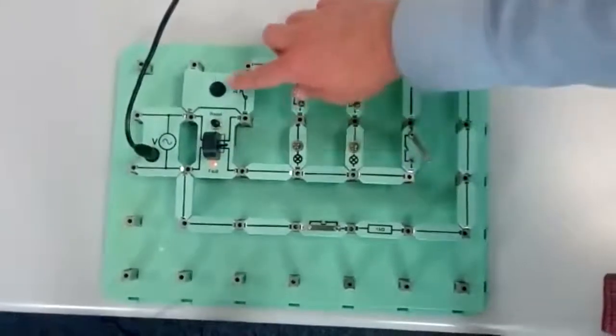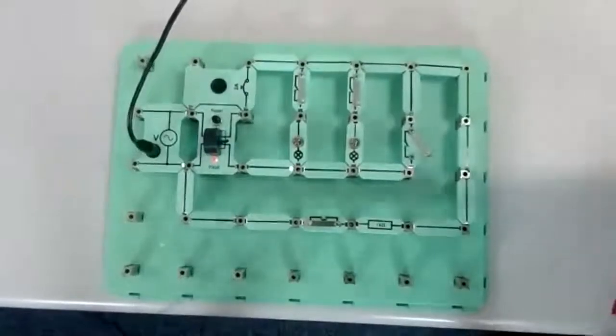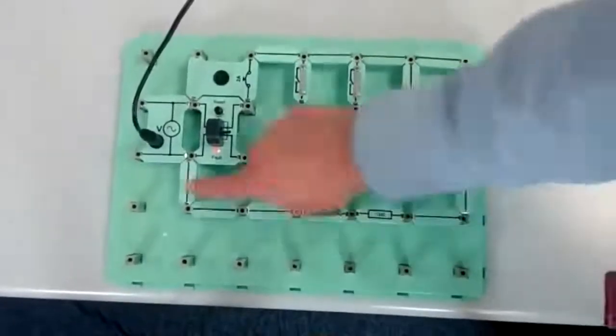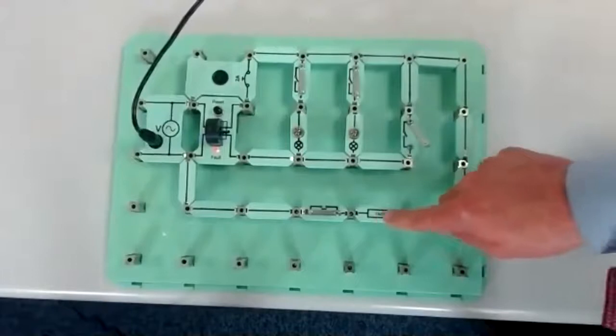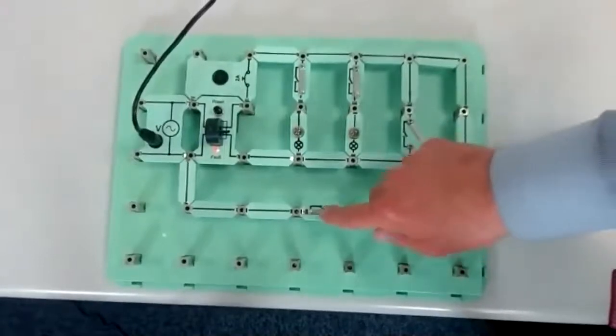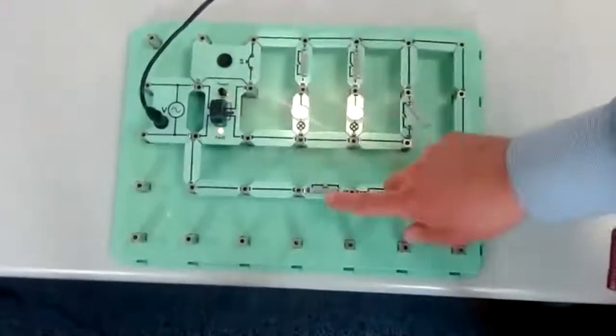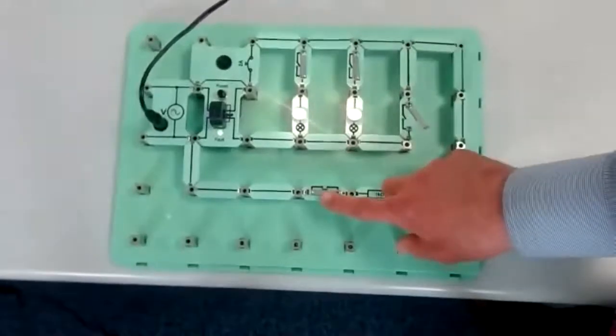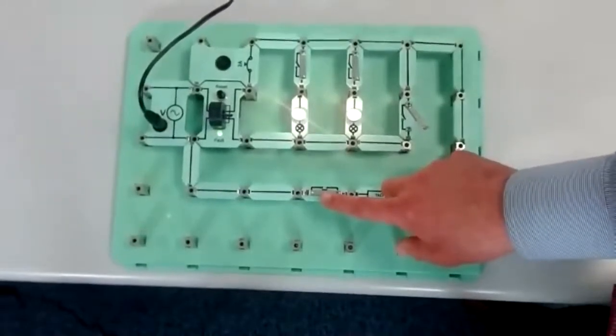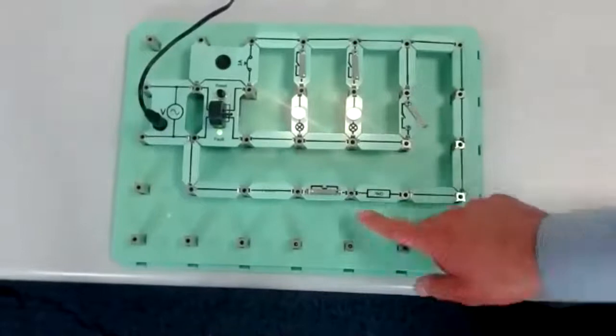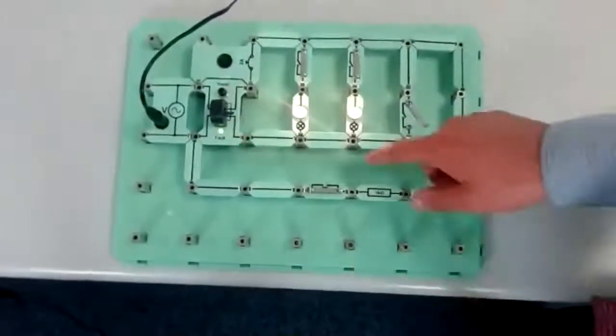So here you've got an RCD, here you've got a fuse board. Now, this goes back to the power. This here you've got a 1K resistor, and here is a push-to-make switch. If you push down on that switch, it simulates an earth leak, a leakage, and thus there will be an imbalance on the RCD. So the RCD, there's a light there you can see.